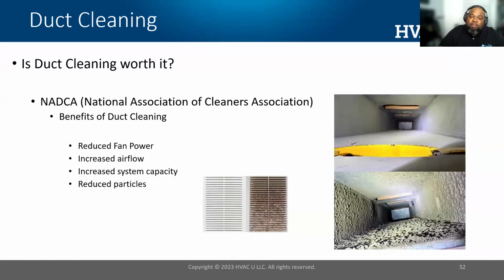Some people may ask, is it worth it? And in my experience, it is. So, some of the benefits coming from NADCA, the National Air Duct Cleaners Association, you have reduced fan power, where the air handler or thing circulating air uses less energy to do its job. You have increased airflow, increased system capacity. Your system can do more work and it reduces particles.